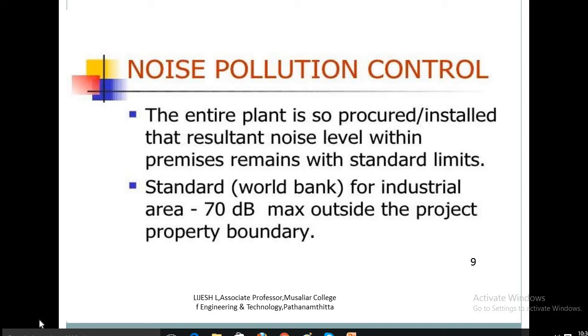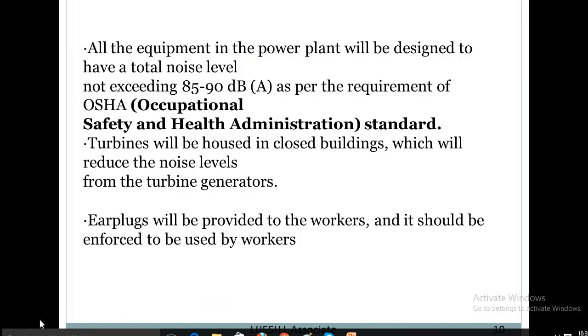Noise pollution control: The entire plant is to be procured or installed such that resultant noise levels within the premises remain within standard limits. The standard for an industrial area is 70 dB maximum outside the project property. All equipment in the power plant will be designed to have a total noise level not exceeding 85 to 90 dB as per OSHA (Occupational Safety and Health Administration) requirements. Turbines will be housed in closed buildings to reduce noise levels from turbine generators.